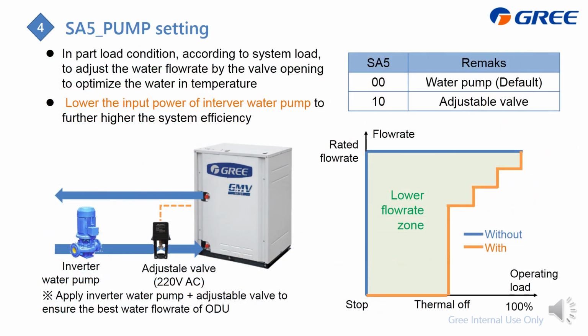This is the detail of the SA5 pump setting. In part load condition, according to the system load, the outdoor unit control program can adjust the water flow rate by the valve if connected, to optimize the water flow rate according to the temperature. The purpose is to lower the input power of the inverter water pump.